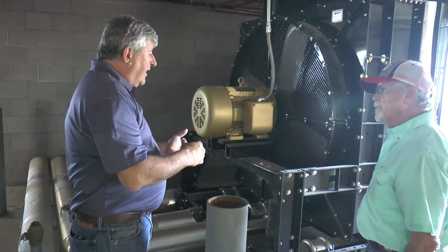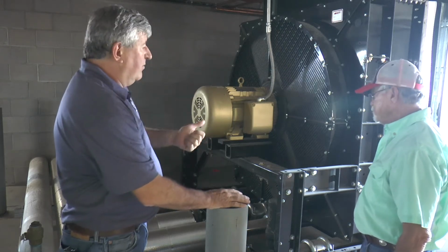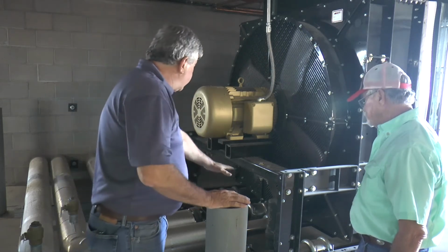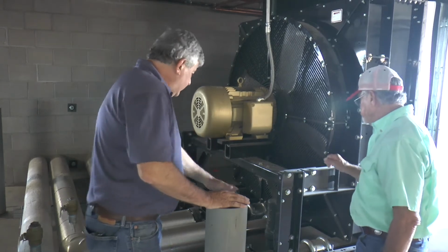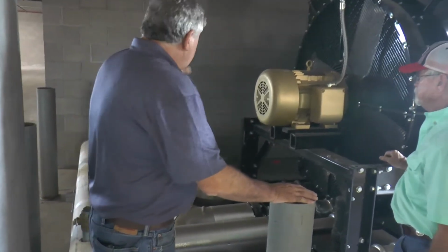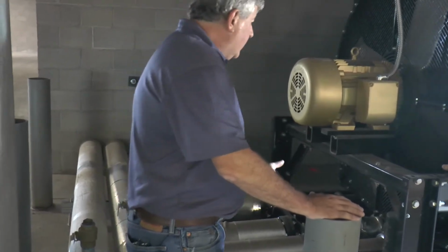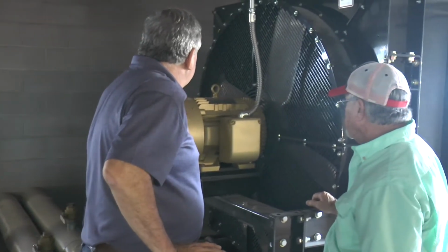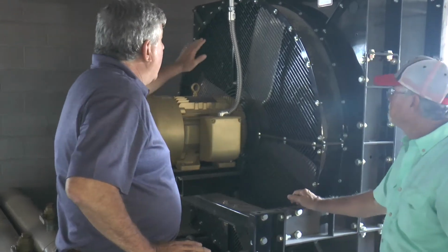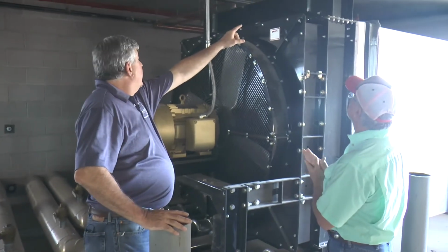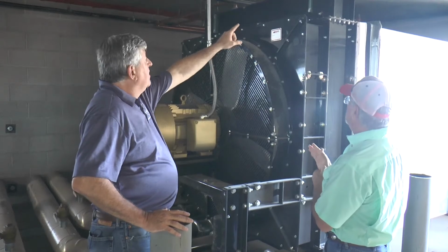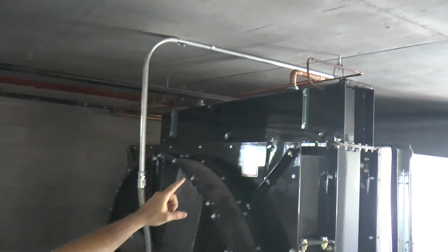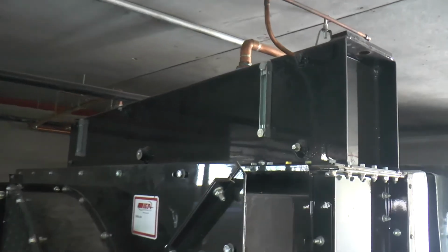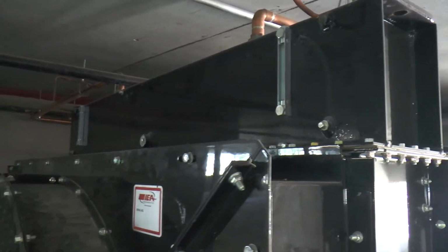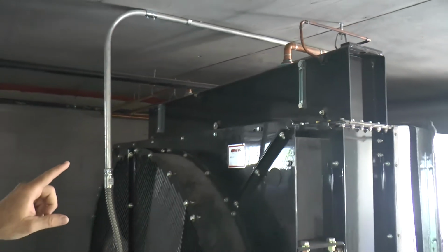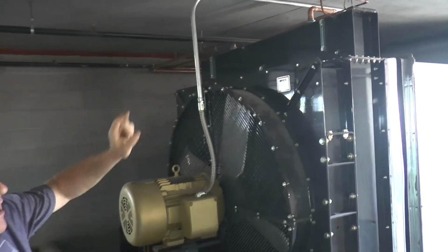So in that respect, when you're doing your inspections, you just want to do a cursory inspection of all the fittings, all the piping going through the wall to make sure that there's no coolant leaks. In service, basically probably once a year, do your grease on your controls. There's a sight glass for both sides of the tank. One side of the tank is for charge air cooling. The other side of the tank is for jacket water. And there's a sight glass for each one of those surge tanks, the tanks there for water level.